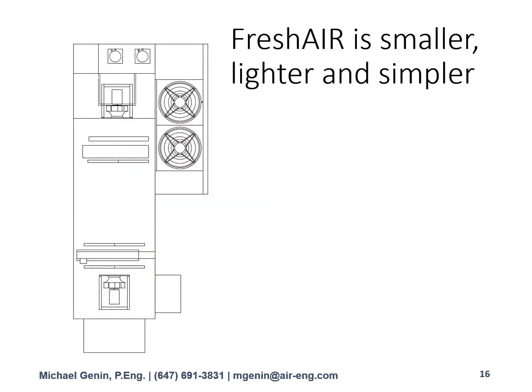Another great benefit of fresh air is that it has a much better footprint. Like we discussed, we only have one mechanical system in this unit to maintain, compared to a traditional unit which would have multiple systems. In this example, we have a unit with compressors, supply and exhaust fan. The heat wheel section is here, and here's our DX cooling. In this case, it has electric supplemental heating. So this is a comparable unit in terms of achieving the exact same performance as a fresh air unit.